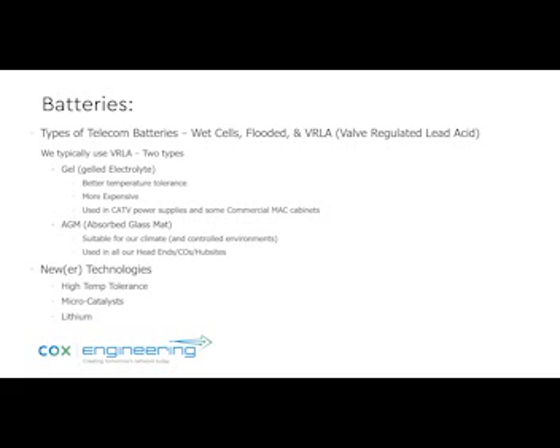Now, in the critical facilities - well, not at Cox, but a lot of the telcos did wet cells, also called flooded, or not valve regulated but vented lead acid. Those are the ones that, especially if you were in the military, you may know of as well, or in utility switching stations, where you have to take the specific gravity, and they're in clear, square, typically large containers.